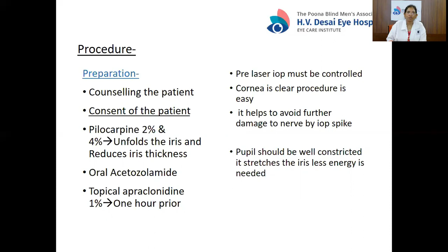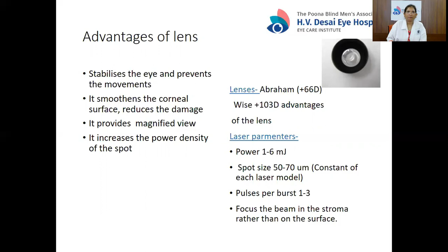The advantages of the lens usage are that it stabilizes the eye and prevents eye movements, smoothens the corneal surface and reduces damage to the cornea. It also provides a magnified view and increases the power density of the laser spots. The laser parameters are power 1 to 6 millijoules, spot size 50 to 70, pulses per burst 1 to 3. Here the focus of the laser beam should be in the stroma rather than on the surface so that the laser will be utilized better.